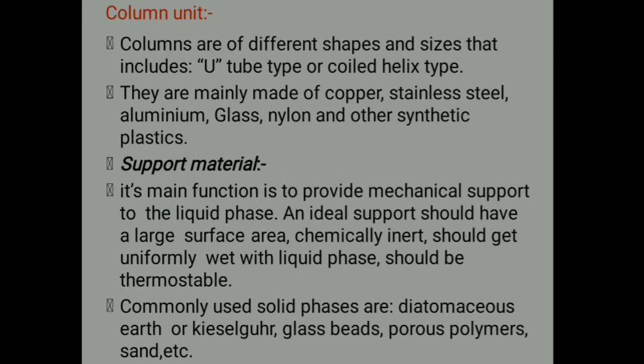Next we have column units. Columns are of different shapes and sizes, including U-type or coiled helix type. They are mainly made up of copper, stainless steel, aluminum, glass, nylon, or other synthetic plastics. Support materials: their main function is to provide mechanical support to the liquid phase. An ideal support should have a large surface area, be chemically inert, should get uniformly wet with the liquid phase, and should be thermostable. Commonly used solid support materials include glass beads, porous polymers, and sand.